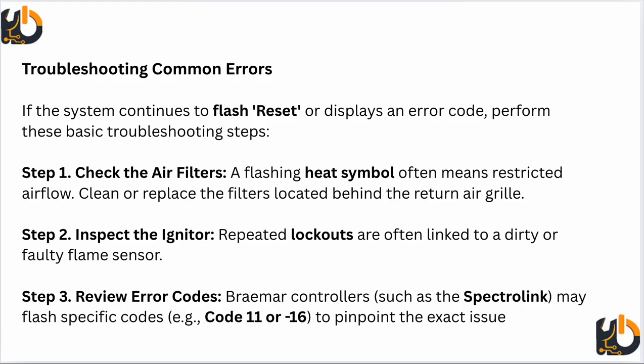Next, step 2, inspect the igniter. Repeated lockouts are often linked to a dirty or faulty flame sensor. Step 3, review the error code. Braemar controllers such as the Spectrolink may flash specific codes like code 11 or 16 to pinpoint the exact issue.